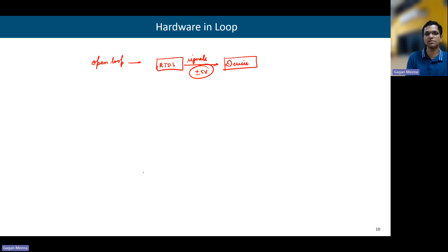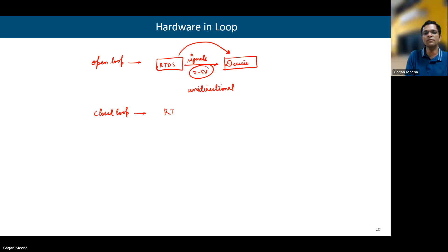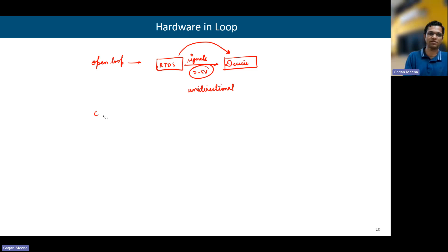In closed loop, the loop is closed. Signals from RTDS go to the device, and the response of the device is fed back to the RTDS. This hardware in loop test can be of two types: control hardware in loop and power hardware in loop. In power hardware in loop, there is an exchange of power between the RTDS and the hardware setup.